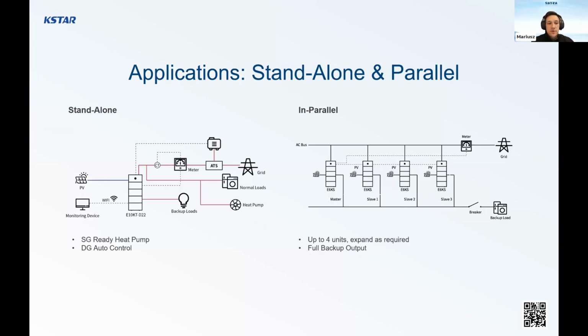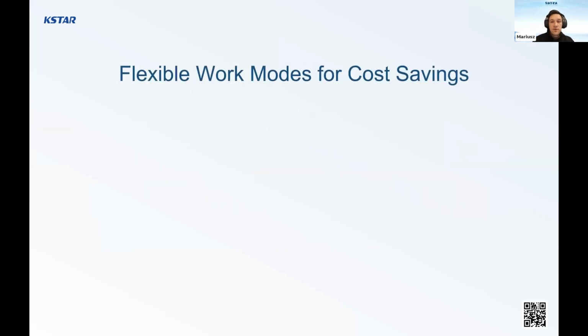At standalone, we are also providing an SG-ready heat pump, and as well in parallel, but because this function is connected just to the master, I will mention the SG-ready heat pump later. And DG auto control is to control the diesel generator in case of really long power outages. In parallel, as I said, we can connect up to 4 units and expand as required with a full backup output. So if we have a 10 kilowatt backup output for one inverter, we can work with 40 kilowatts output with 4 inverters, which I think is enough for most households.